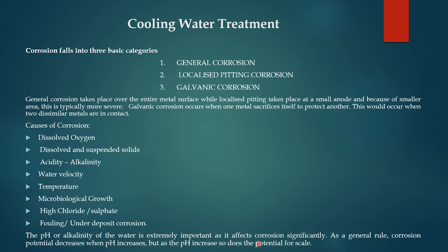The pH or alkalinity of the water is extremely important as it affects corrosion significantly. As a general rule, corrosion potential decreases as pH increases, but as pH increases so does the potential for scale, because the scaling value will be high as pH increases.